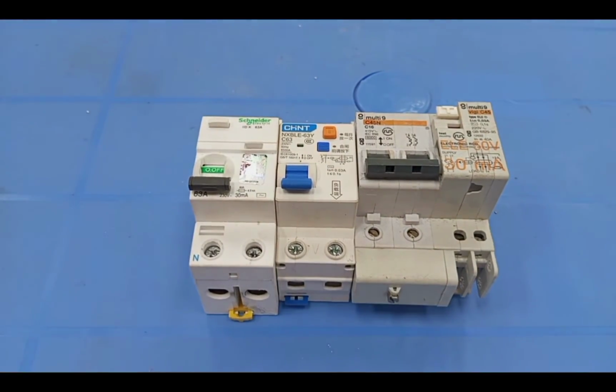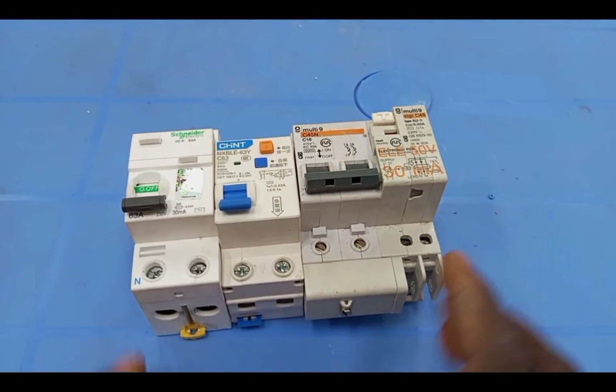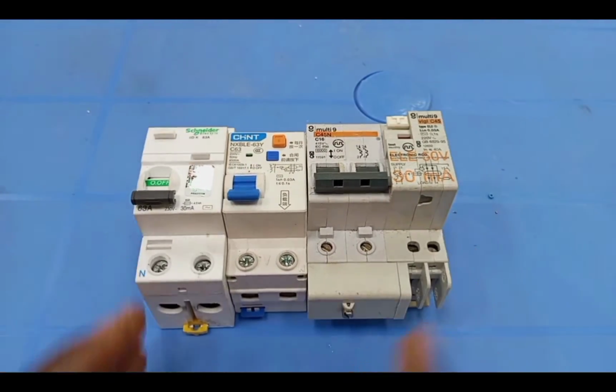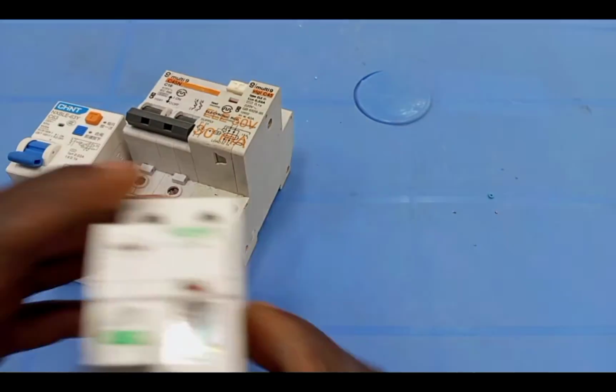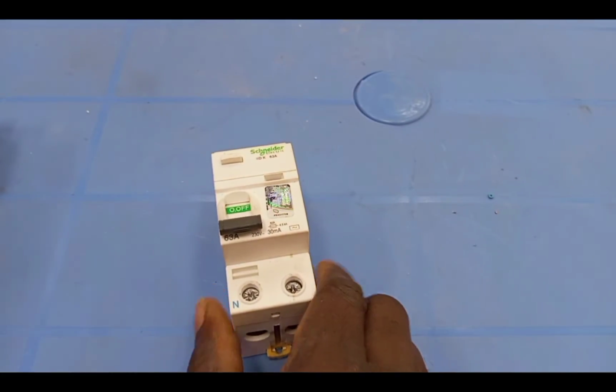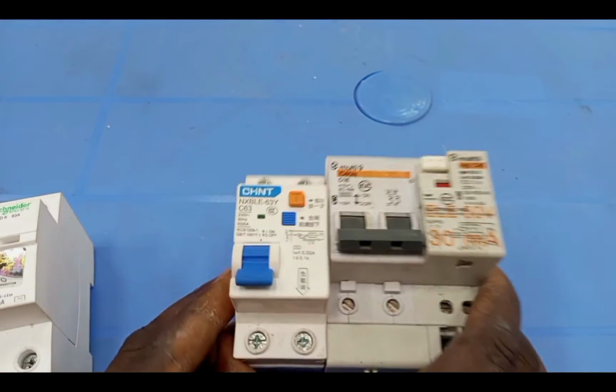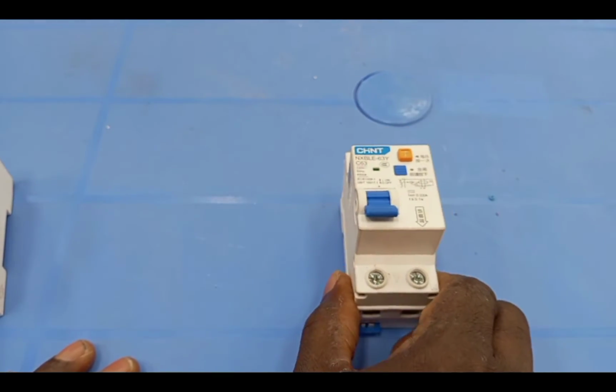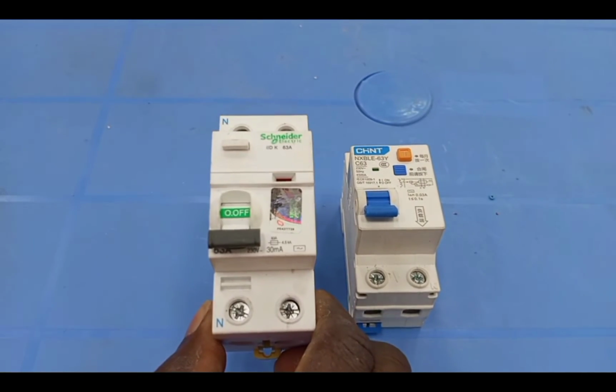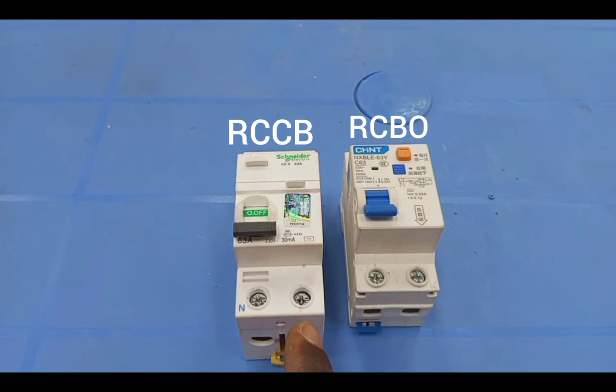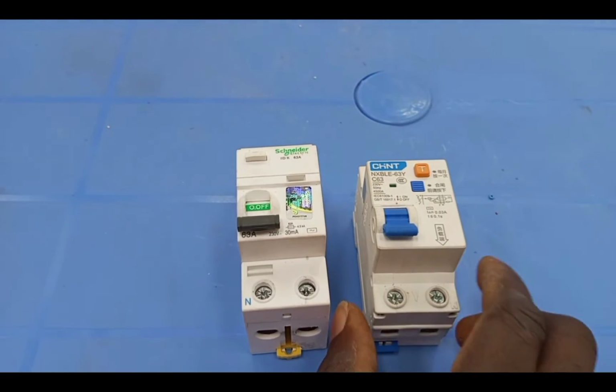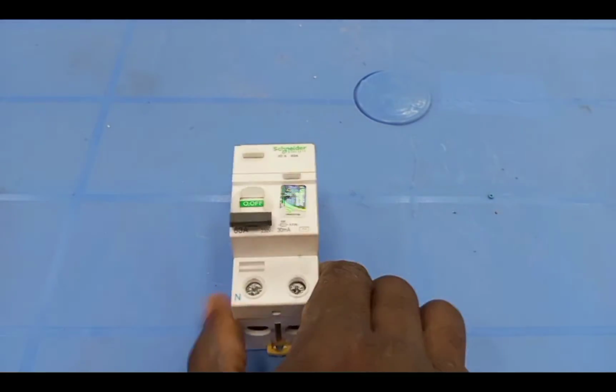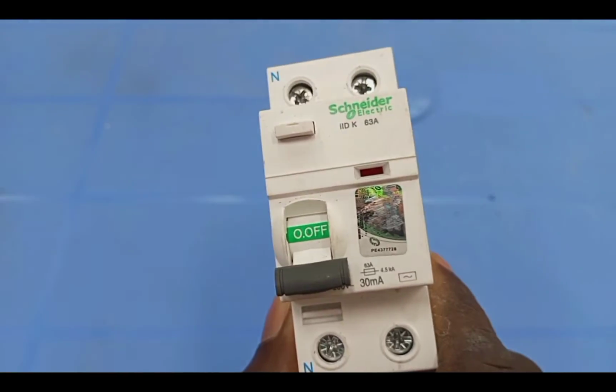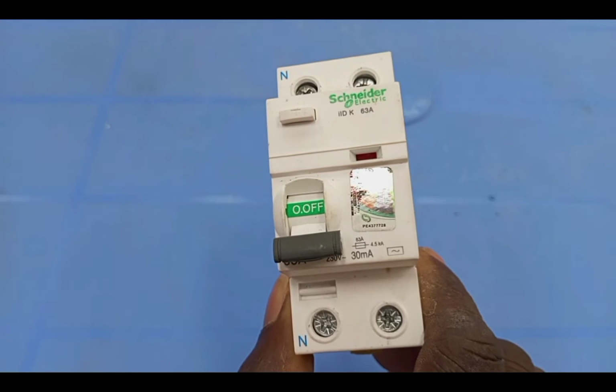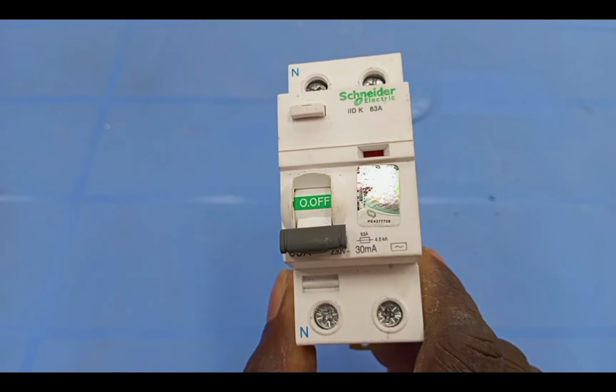The next thing I'm talking about is the residual current device. So all these three are residual current devices. But then we have the RCCB, and then we have the RCBO. Now, this is an RCD. This is also an RCD. These two, how do they work? So let me first talk about the RCCB. So RCCB stands for Residual Current Circuit Breaker.